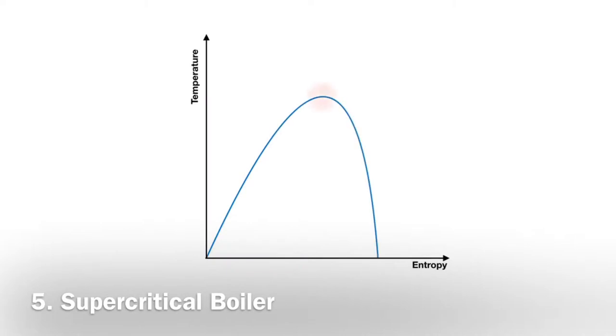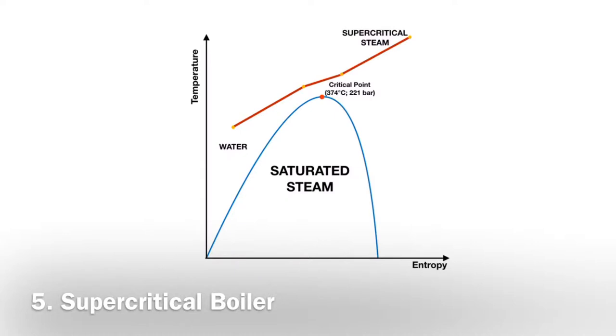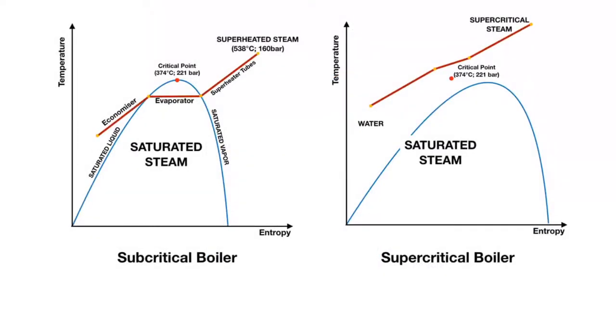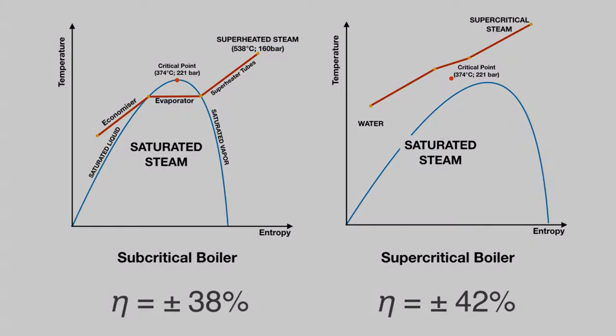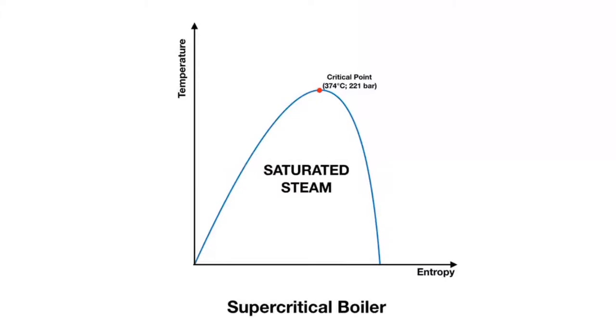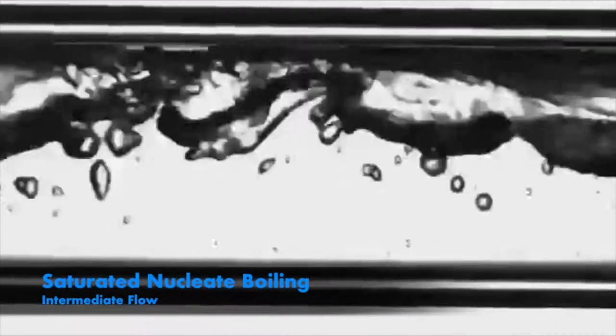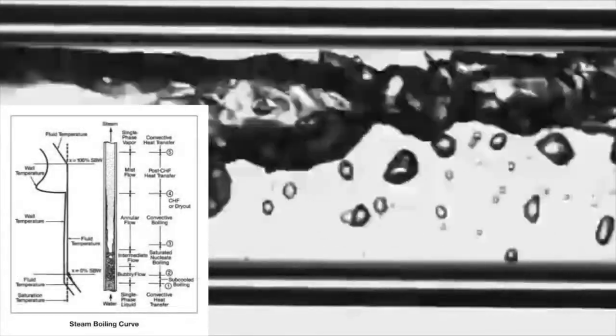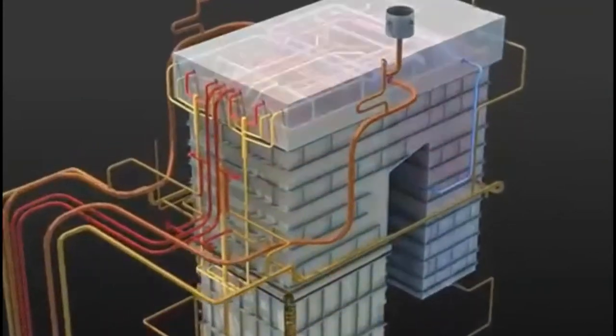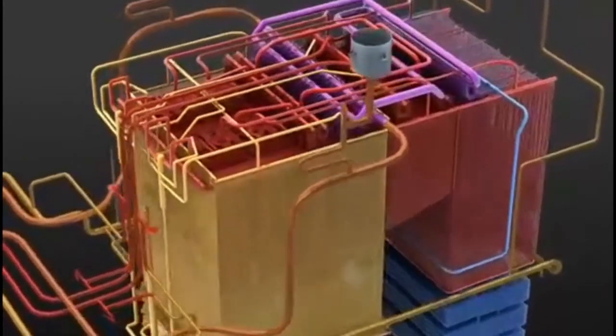Supercritical boiler. If a boiler works above its critical point, it is called a supercritical boiler. Supercritical boilers have better fuel efficiency than subcritical boilers — around 42% design efficiency, while subcritical boilers can only reach 38%. This is due to the impossibility of forming saturated steam in the supercritical cycle. Above the critical point, water does not experience the nucleate boiling phase — the transition from liquid to steam. One main characteristic of supercritical boilers is the absence of a steam drum, which is present in subcritical boilers to separate water from saturated steam.